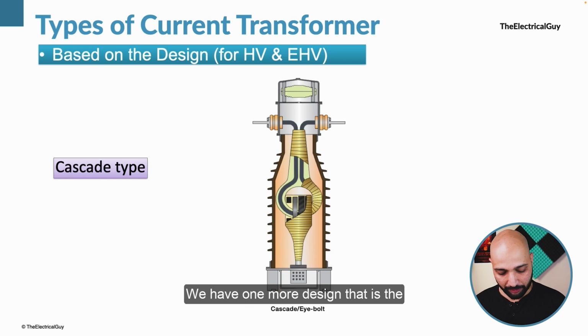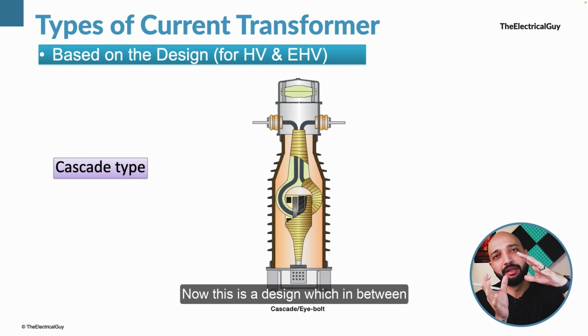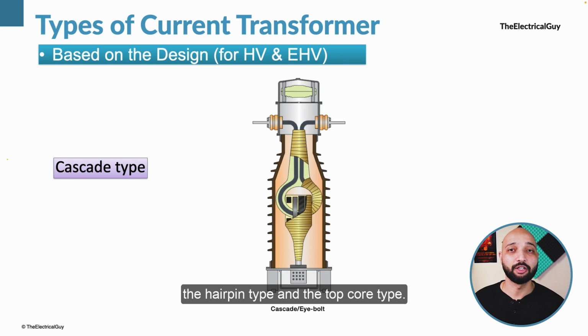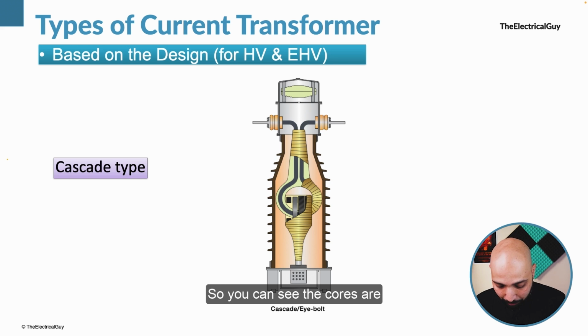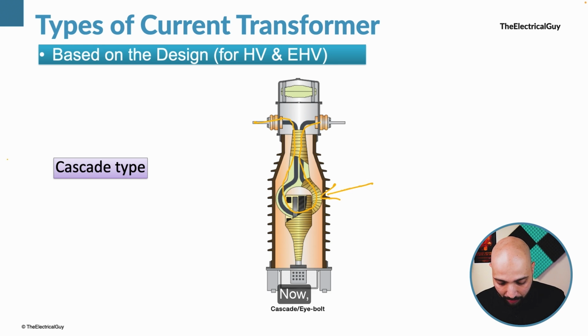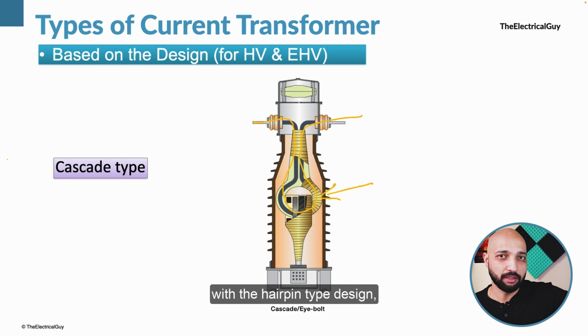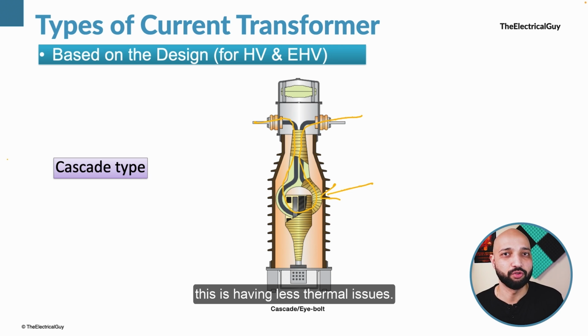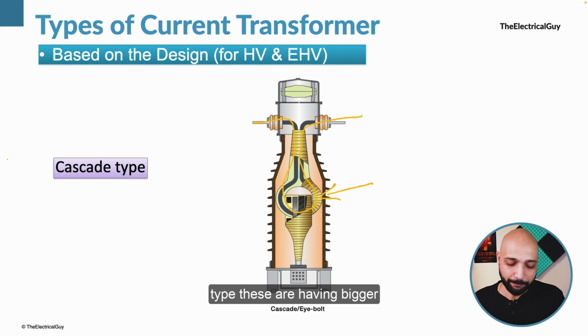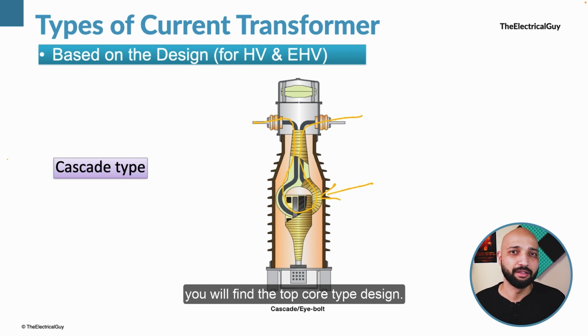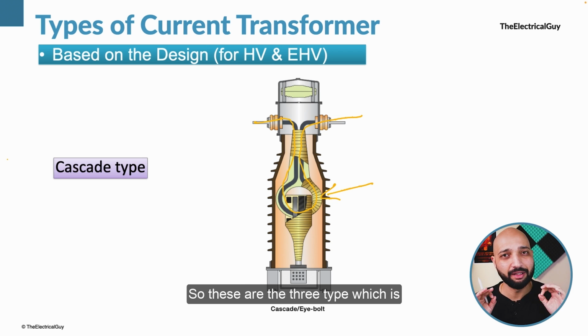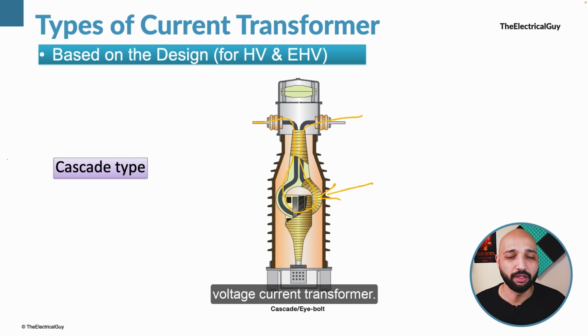We have one more design, that is the cascade design or the eye bolt design. Now this is a design which is in between the hairpin type and the top core type. So this is in between. You can see the cores are placed at the center, and this is how the primary conductor is going. Now when we compare the thermal issues with the hairpin type design, this has fewer thermal issues. But when we compare it with the top core type, it has bigger or more thermal issues. Again, this type of current transformer you won't find very frequently. Majorly you will find the top core type design, right? Understood. So these are the three types which are specific to high and extra high voltage current transformers.